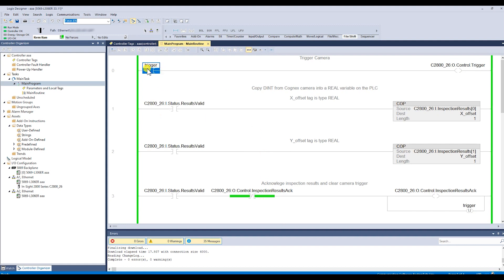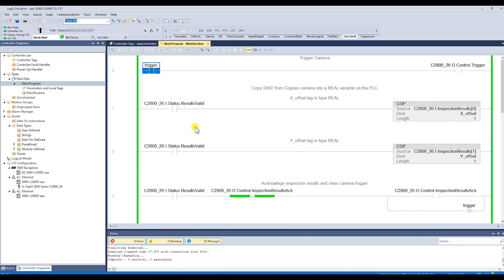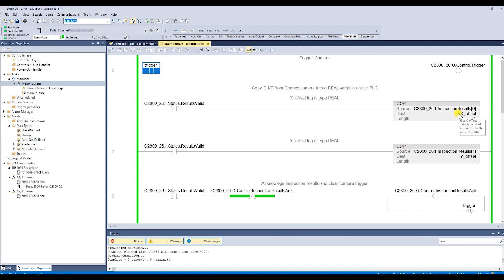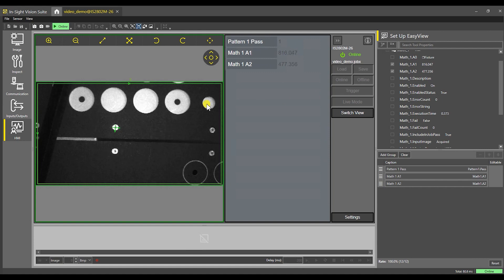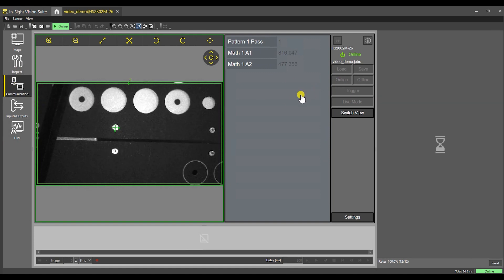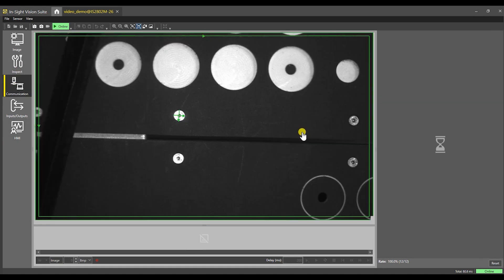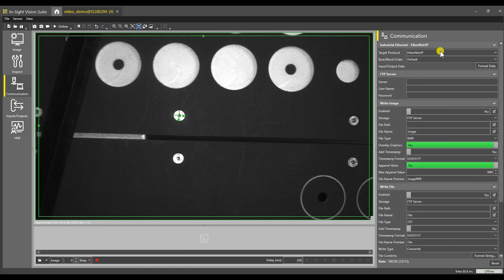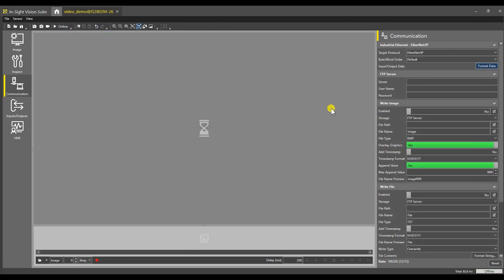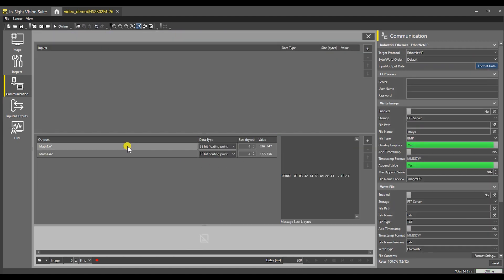For those that don't know what PLC logic looks like, this is what it is. It is doing these steps in sequence. When that went true, it turned on the trigger for the camera. Once the camera said hey, my results are valid, it will copy the value from inspection results into a variable called X offset, the same thing for Y, and copy that. Remember, in our communication we set things up so that X was first and Y was second.